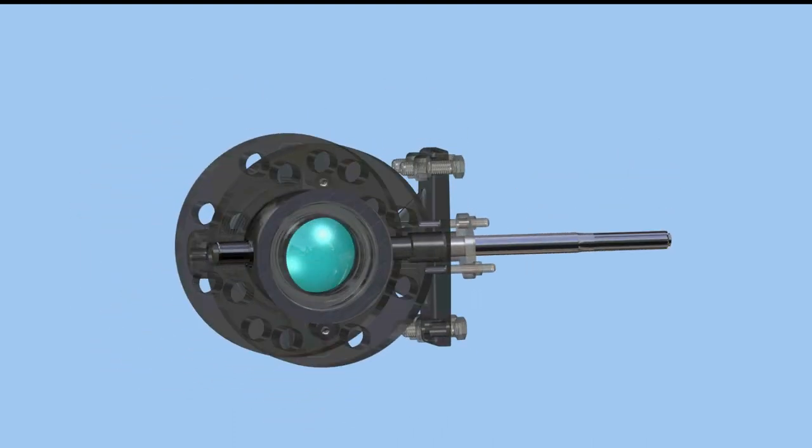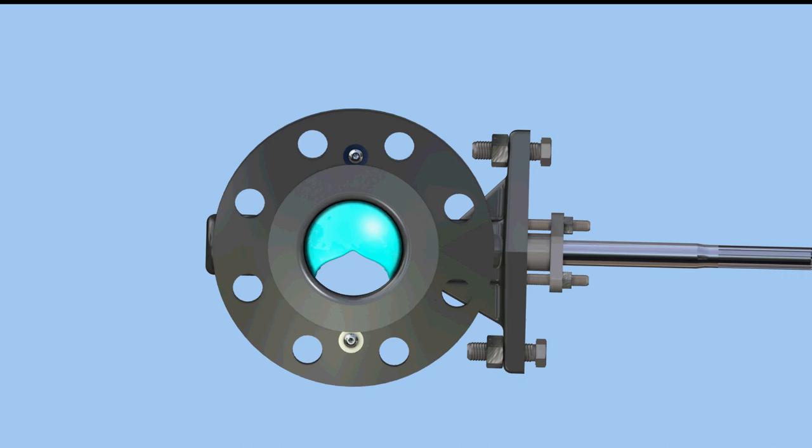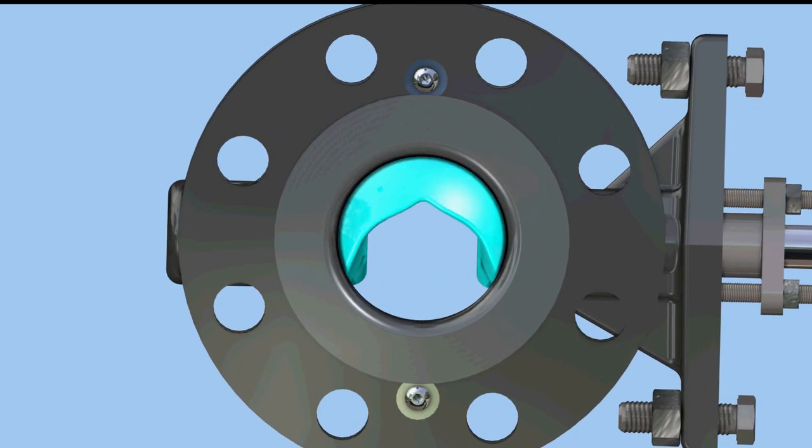As the drive shaft is rotated, the ball rotates to expose a flow path through the V notch. This V notch allows for a large flow range due to a small flow area at low travel and a large flow area at maximum travel.